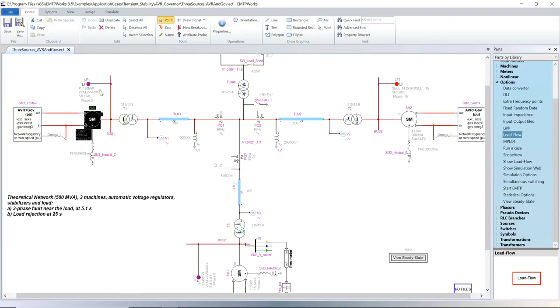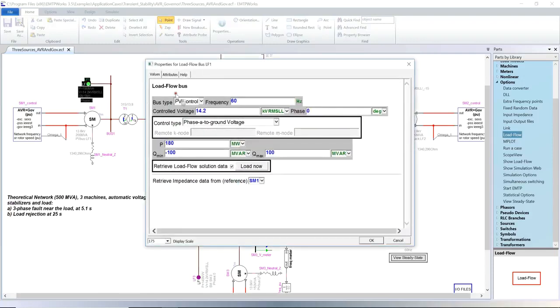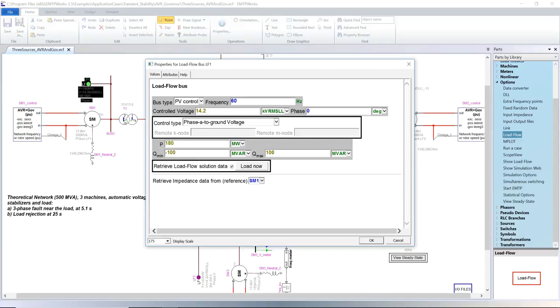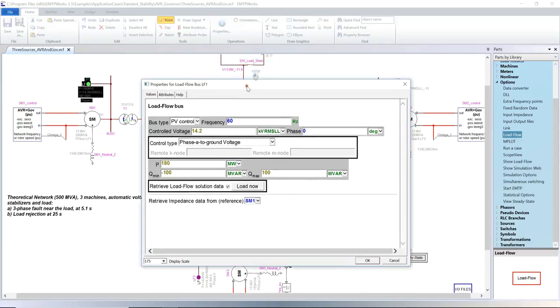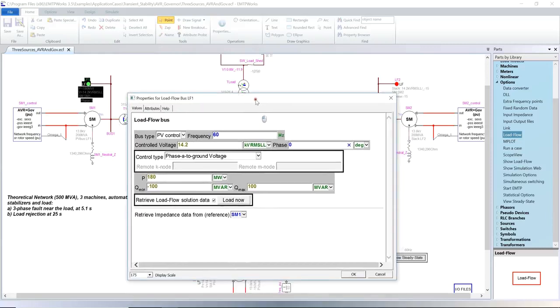In the load flow bus, select PV and link with the synchronous machine. Enter the power and voltage references according to the contingency. If these limits are reached during the load flow calculation, the PV bus is transformed into a PQ bus. The voltage phase input does not have to be provided. The value entered here will be used for the first network iteration.